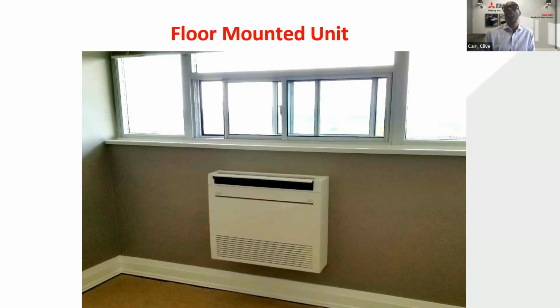Overall, what I'm saying is you can't go wrong with cold climate air source heat pumps. But I'd have to say what you just brought up about the controls is such a critical piece, because that is something that is continuing to evolve and is, I think, the game changer in the application of air source heat pumps. Previously it was: the furnace gets turned on at this point, the air source heat pump gets turned on at that point. But now you have algorithms in the background calculating everything based on cost, or, we've got some homeowners who want to do it just based on the carbon, not even the cost. Because they are so cost efficient, a lot of the time they're okay spending an extra $100 as long as they're optimizing on the carbon side of things. So you can do some programming based on that.